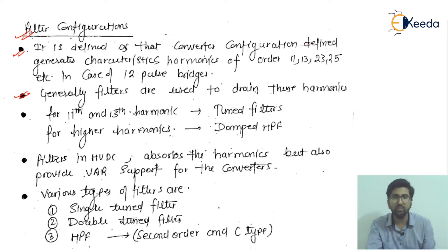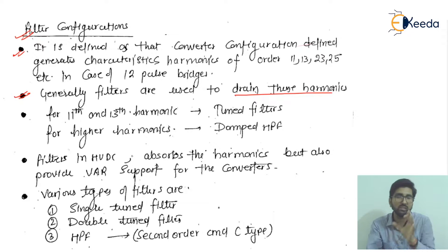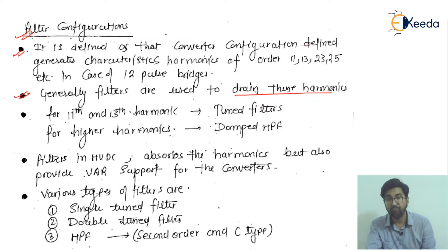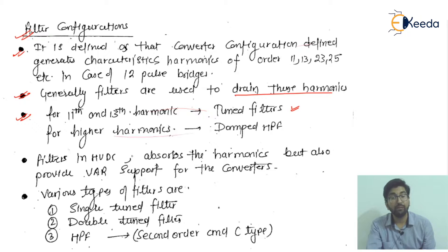Generally, filters are used to drain these harmonics. Filters are designed in such a way that they can drain or filter out these characteristic harmonics from the systems, or suppress them. For 11th and 13th harmonics, we generally use tuned filters, and for higher-order harmonics, it is called damped high-pass filters.